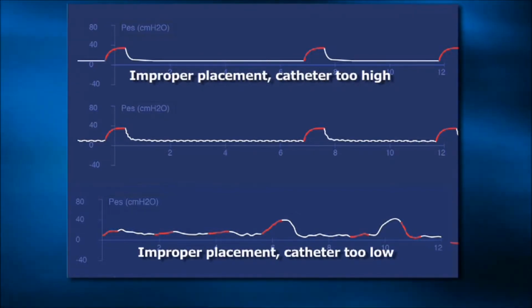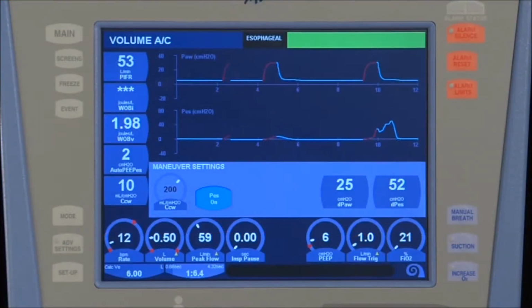Once placed, catheter position can be verified by cardiac oscillations in the esophageal waveform or by chest radiograph. As the placement process is completed, review baseline airway and esophageal pressure waveforms. The ventilator will now begin breath-by-breath measurements on some parameters and requires a maneuver to obtain others, such as lung and chest wall compliance.